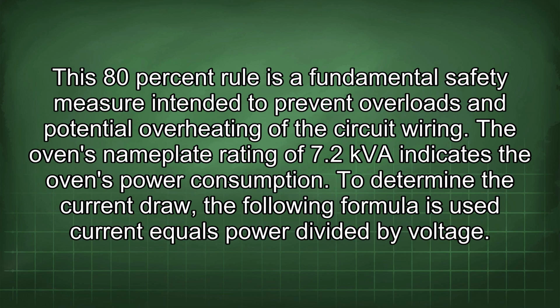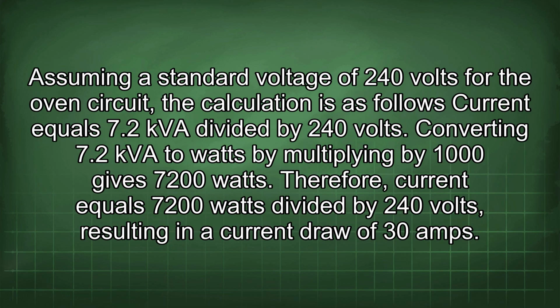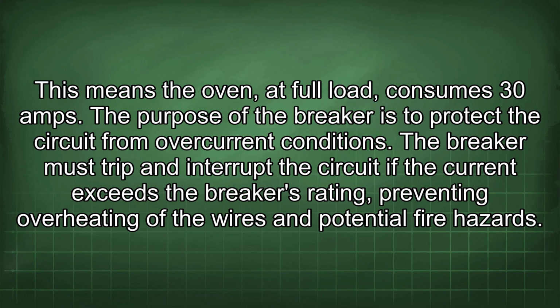The oven's nameplate rating of 7.2 kVA indicates the oven's power consumption. To determine the current draw, the following formula is used: current equals power divided by voltage. Assuming a standard voltage of 240 volts for the oven circuit, the calculation is as follows: current equals 7.2 kVA divided by 240 volts. Converting 7.2 kVA to watts by multiplying by 1000 gives 7200 watts. Therefore, current equals 7200 watts divided by 240 volts, resulting in a current draw of 30 amps. This means the oven, at full load, consumes 30 amps.